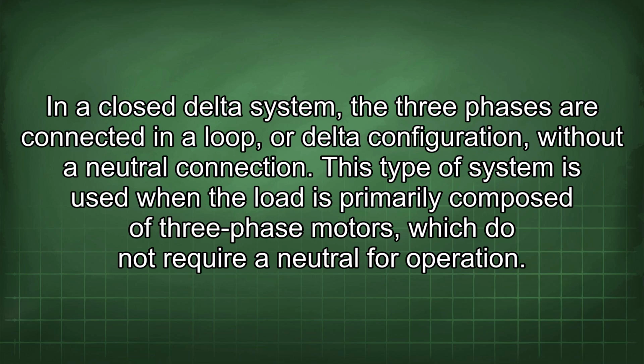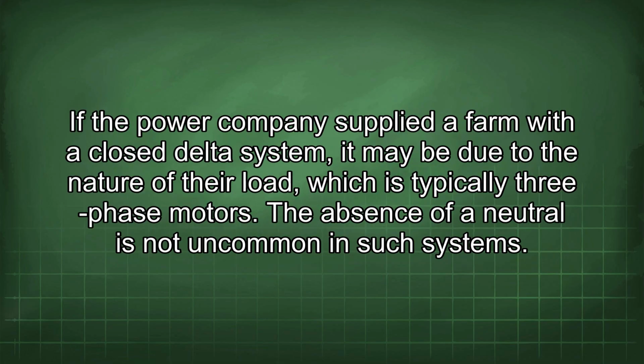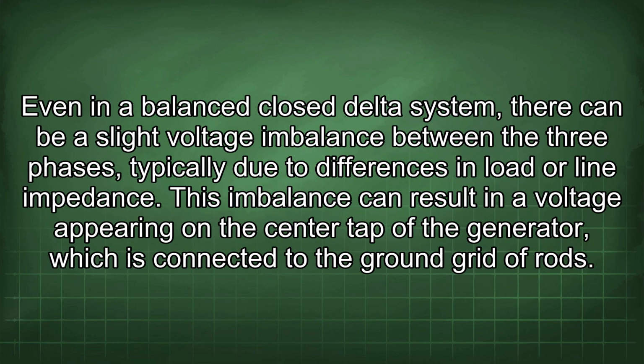This type of system is used when the load is primarily composed of three-phase motors, which do not require a neutral for operation. If the power company supplied a farm with a closed delta system, it may be due to the nature of their load, which is typically three-phase motors. The absence of a neutral is not uncommon in such systems. Even in a balanced closed delta system, there can be a slight voltage imbalance between the three phases, typically due to differences in load or line impedance.